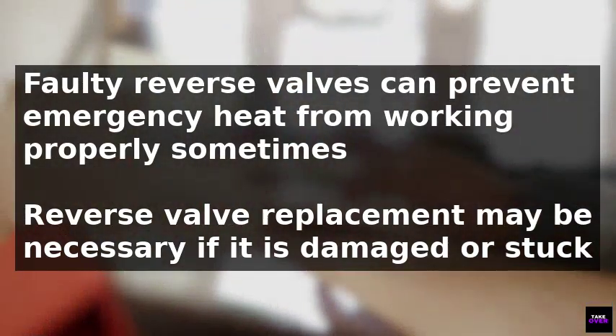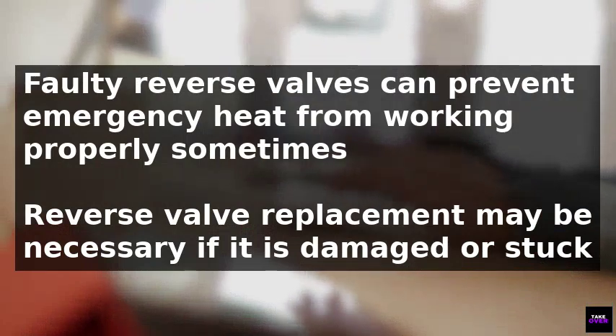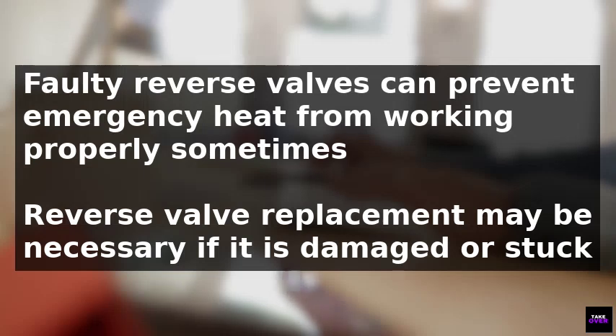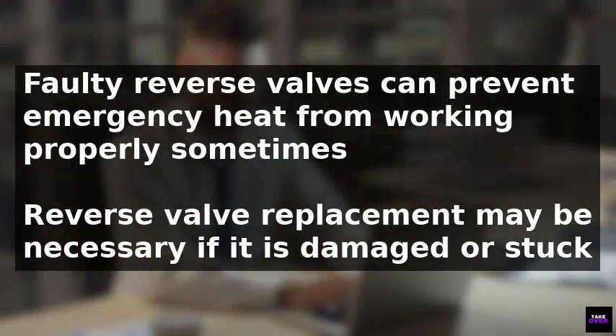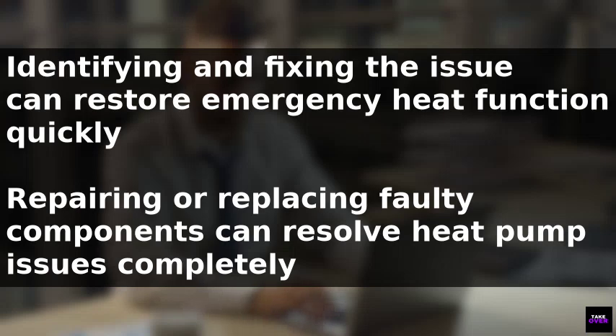A faulty reverse valve is also a possible cause, as this component is responsible for switching the heat pump between heating and cooling modes. If the reverse valve is stuck, it may be possible to fix it by tapping it gently, but if it is damaged, replacement will be necessary.